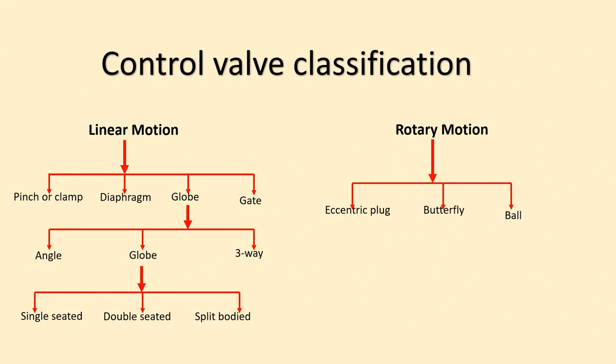Linear motion has different types of valve bodies: pinch or clamp type, diaphragm type, globe type, and gate type. The globe type of control valve is further classified into angle valve, globe valve, and three-way valve. The globe valve is further classified into single seated, double seated, and split body. These are the basic classifications of control valves that fall into the linear motion category.